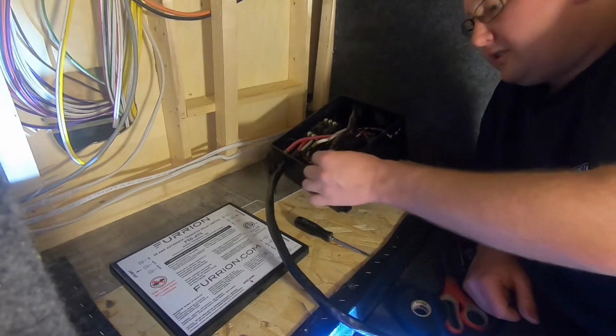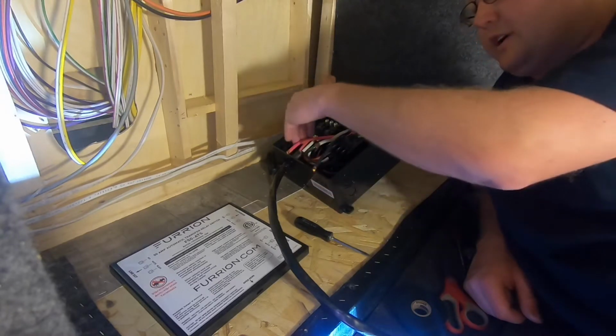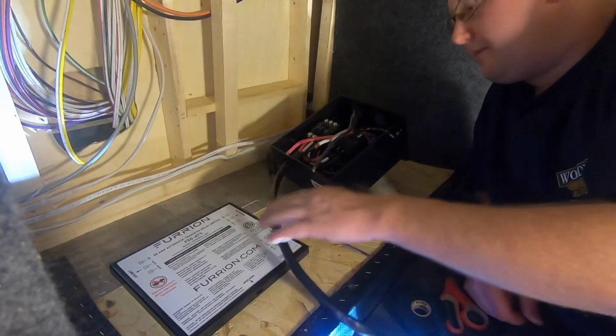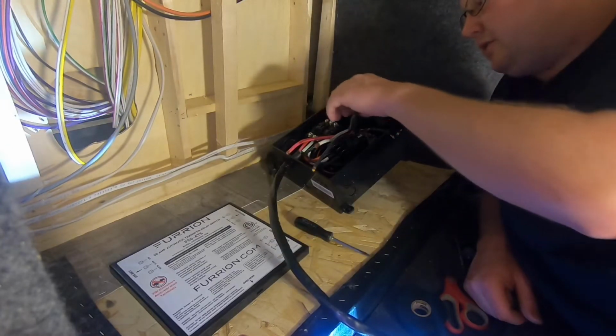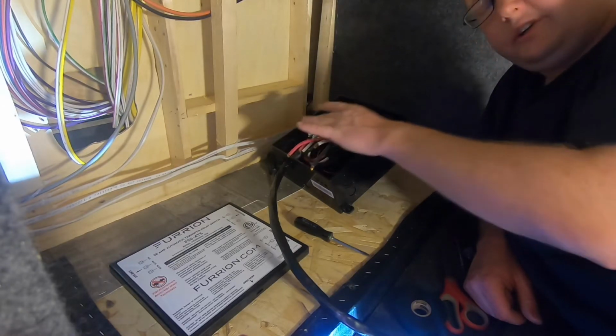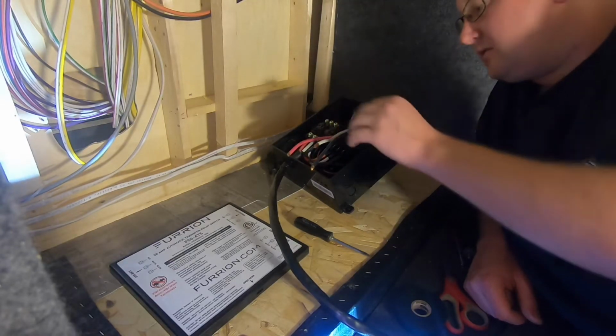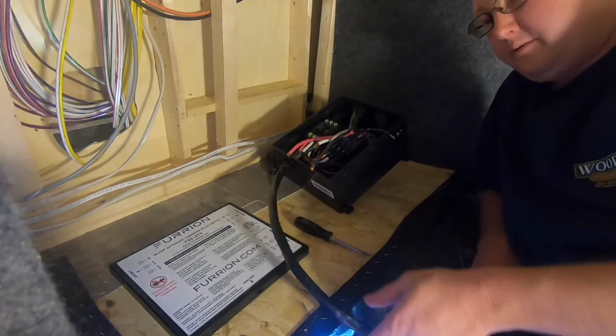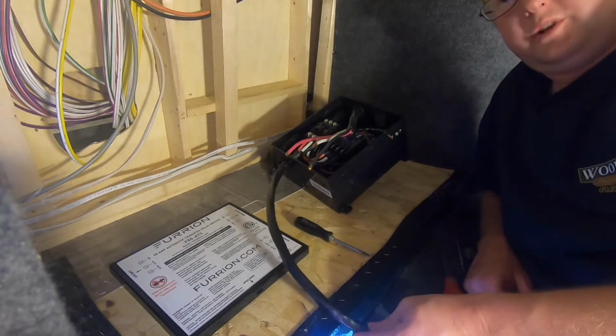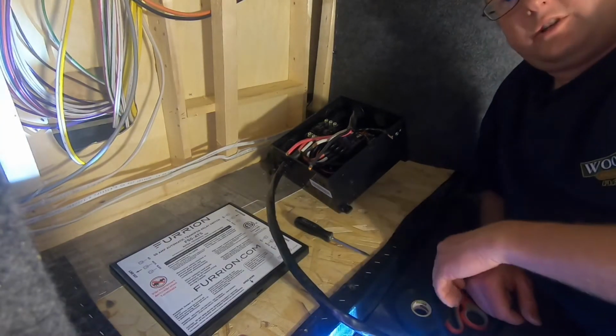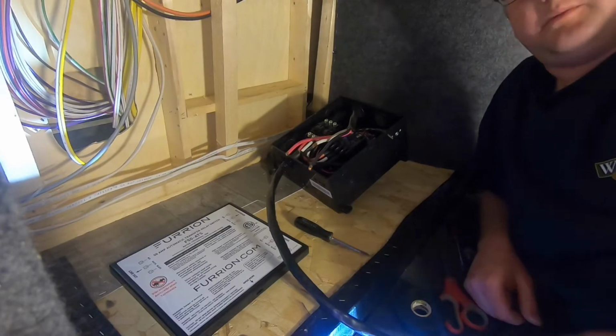So now I'm going to cut these wires down. I got them in the right order: red, white, black. Those are going to plug into these terminals here. Once I get these trimmed down and plugged in, I'll show you exactly what we have, and then we'll feed this wire back through, plug it back into the panel, test the transfer switch, and see if I knew what I was talking about.